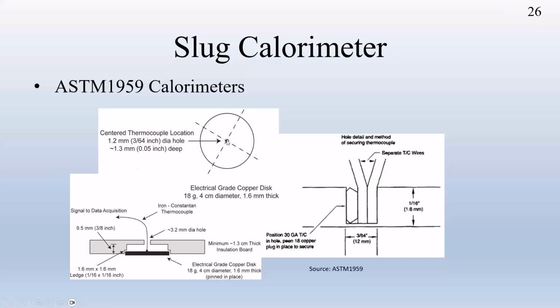So then you drill a hole in the middle, and you put the thermocouple over there, and behind it is the insulator, and the air chamber. Okay, so this way, that temperature rise translates, if you do it at 18 gram, one degree temperature rise equals 0.135 calorie. So that has a direct translation, and then we can measure the temperature rise and get the incident energy.